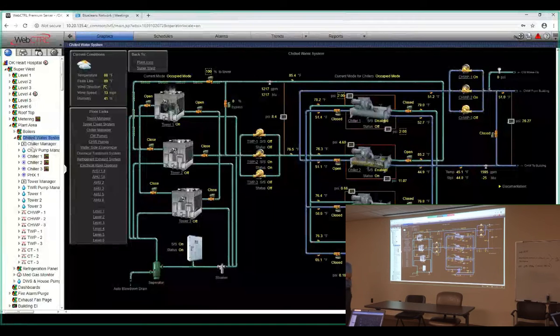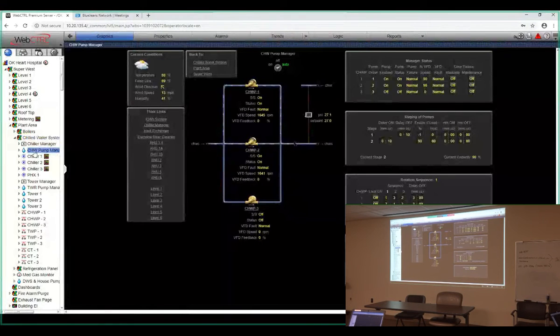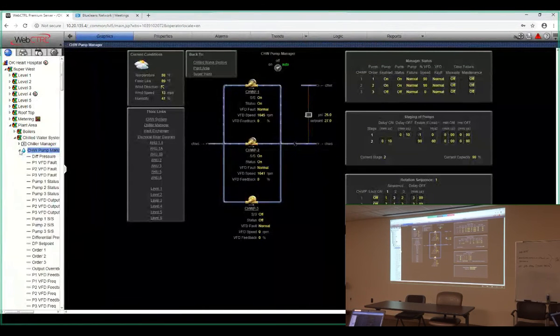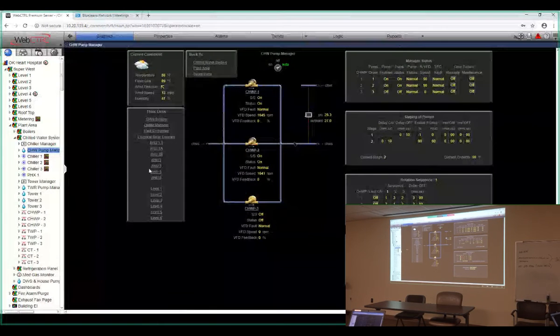All right, let's go to the chilled water pump manager. Same philosophy as the chiller manager. So we have the same rotation information. So rotation, we have a sequence, 1, 2, and 3. What our pump off delays are. And then we can choose again how we want to rotate the chill water pumps. So all of these managers have this same logic behind how they rotate and how they sequence pumps or sequence equipment.